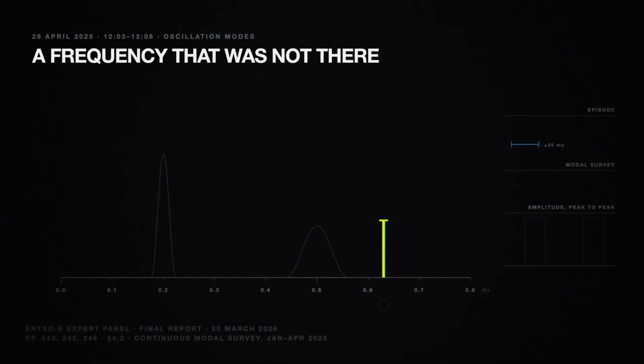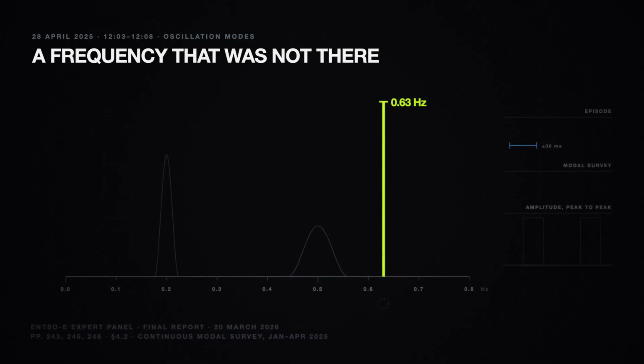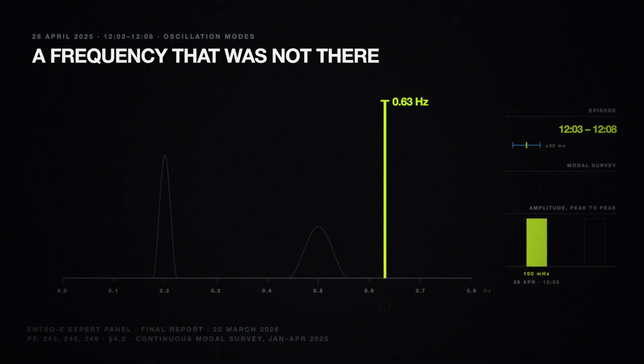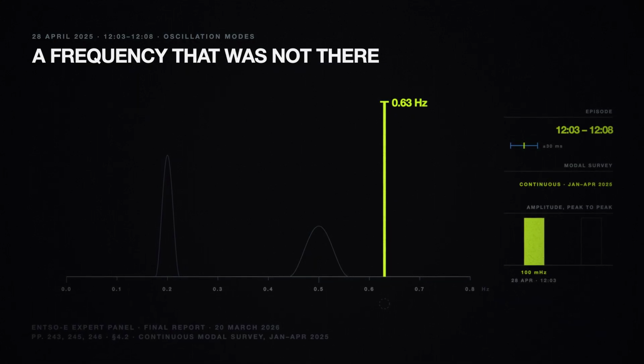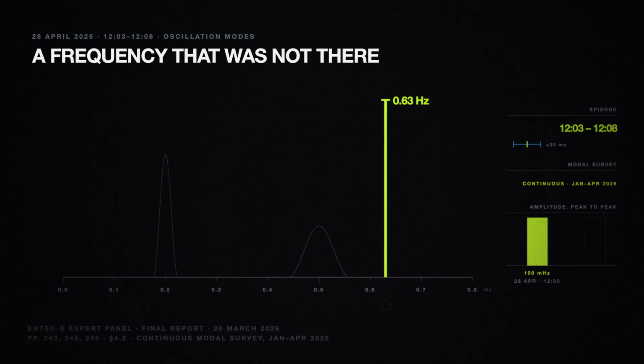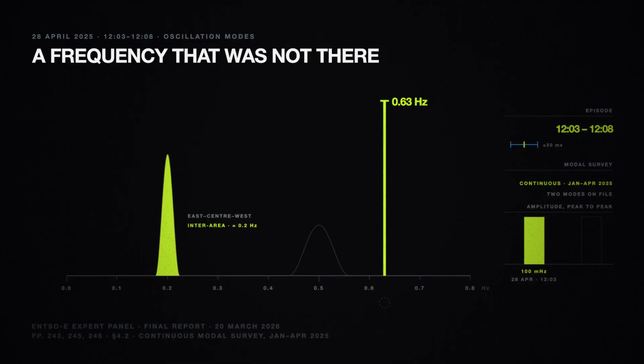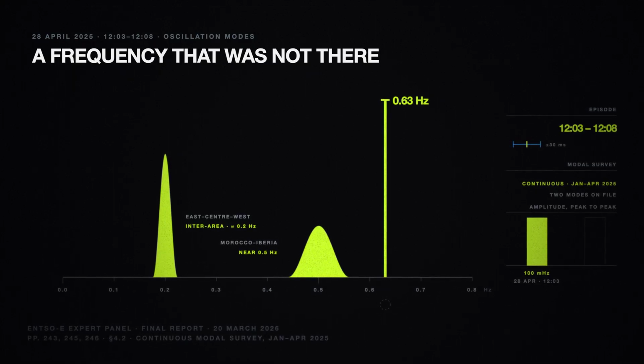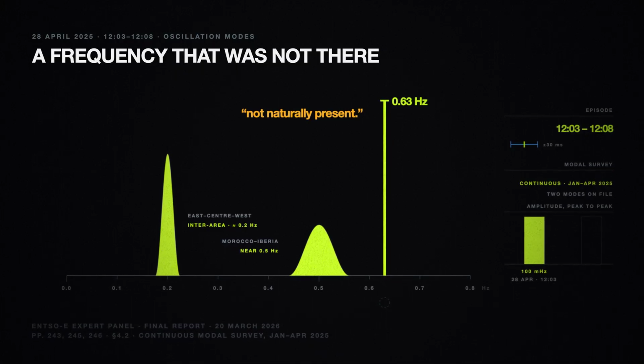3 minutes past 12, on the 28th of April, the Iberian system began oscillating at 0.63 Hz. It ran for 5 minutes, until 8 minutes past 12, at an amplitude of 100 mHz peak to peak. A continuous survey of that system's oscillation modes had been running since January of 2025, recording the frequencies at which the peninsula swings on its own. By April, it had 2 of them on file. The East-Center-West Inter-Area mode at about 0.2 Hz, and a Morocco to Iberia mode near 0.5. Of 0.63 Hz, the report says 4 words, not naturally present.